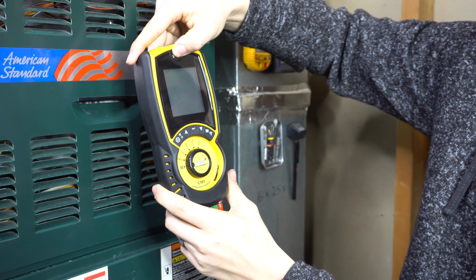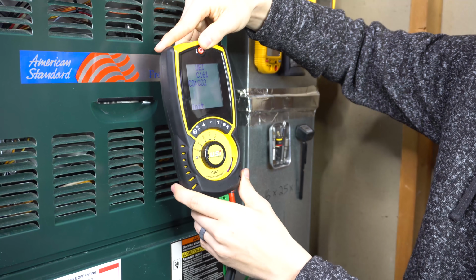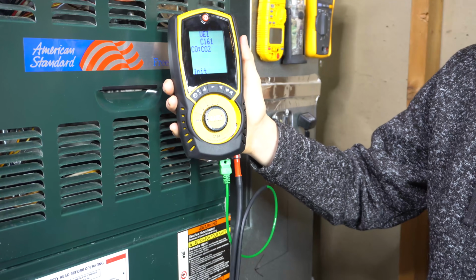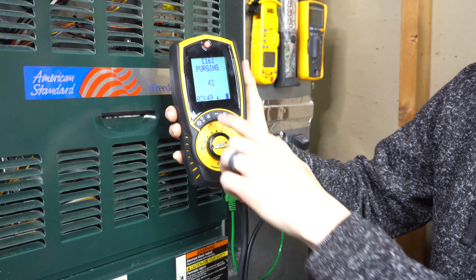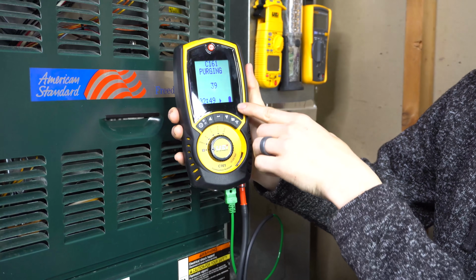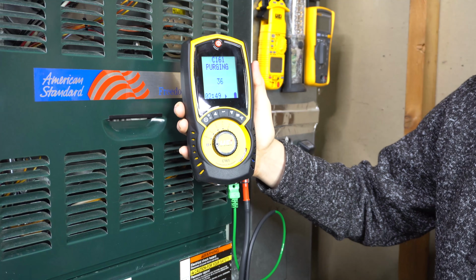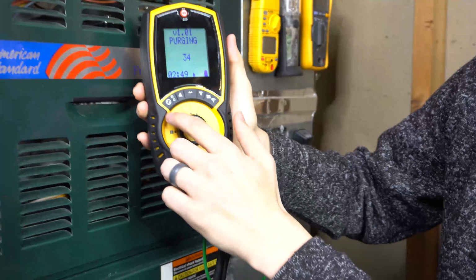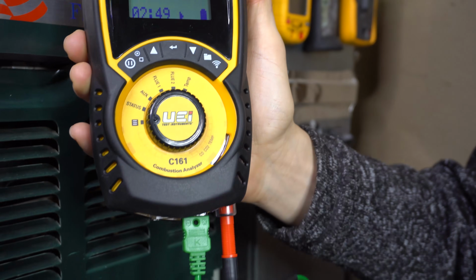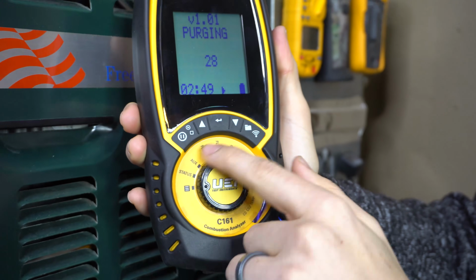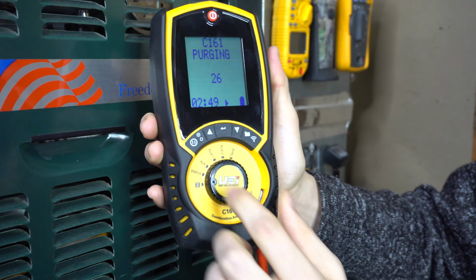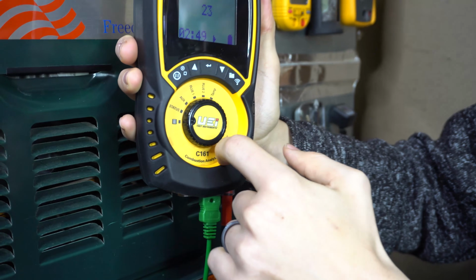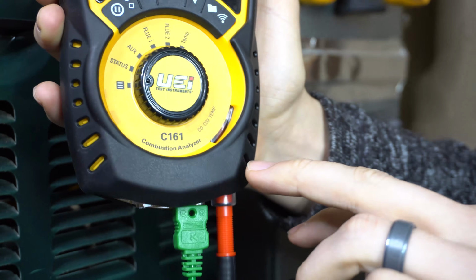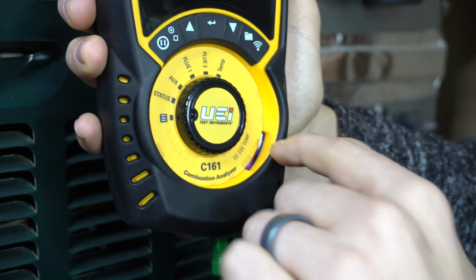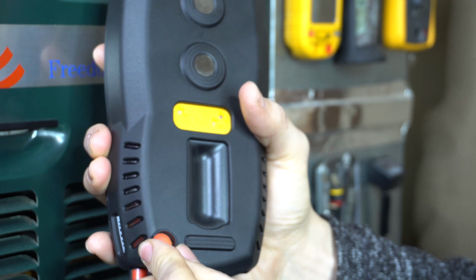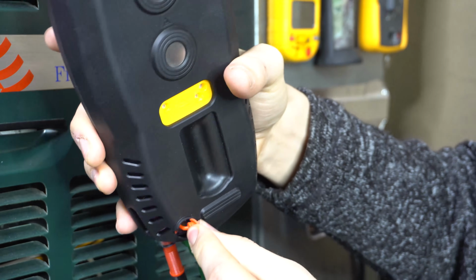And like most other analyzers out there, it has a 60-second purge cycle, which really should be done outside in fresh air. On the bottom here you see the time, then the battery life remaining. And while we're waiting for it to purge, just quickly about the meter, you got the navigation and the function buttons right here. You got the menu options right here that you can select with the dial. Then there's also a little sight glass on the bottom over here. So whenever the water trap fills up with water, you can see it from the front when it gets too high. After it's filled up, you can open up the plug in the back and dump that water out.